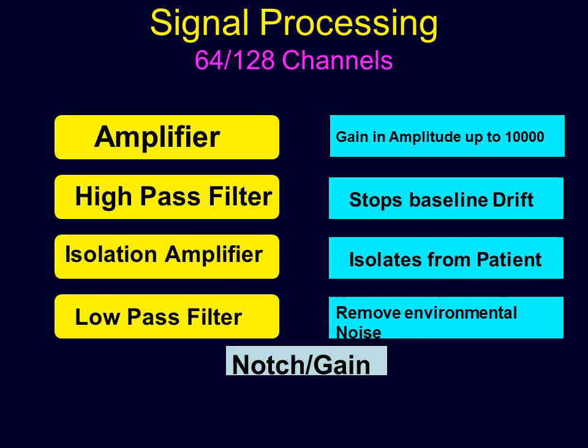If your lab is converted from a cath lab to an EP lab and is not independently grounded from the building, it is not uncommon to get significant noise on the catheters and you may have to put a notch filter on. Personally, I prefer not to use the notch because sometimes you may miss potentials as you try to filter the 60 Hz out of the electrogram — 50 Hz in Europe and 60 Hz in the United States. There is also an analog-to-digital converter for display.